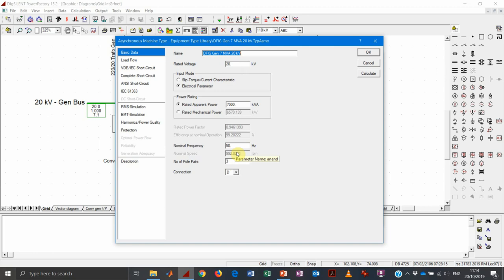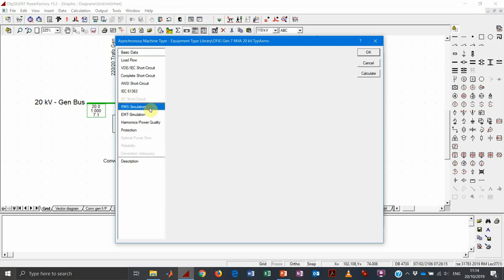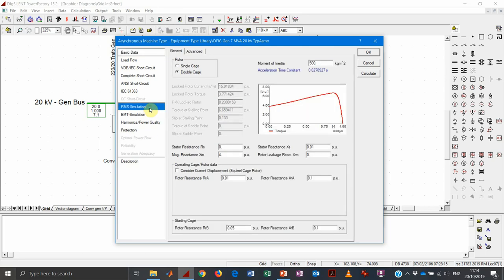That means the nominal rotational speed is a little bit less than 1000 revolutions per minute in the 50 Hz world. It has a double cage characteristic with more or less standard values for a doubly fed induction generator. One interesting element is the moment of inertia, which is around 500 kilogram square meter — normalized on the machine basis that corresponds to a little bit less than one second of acceleration time.